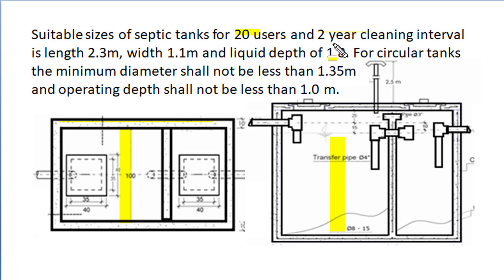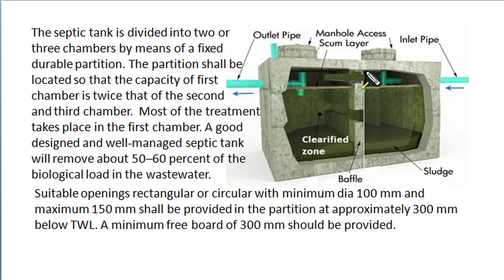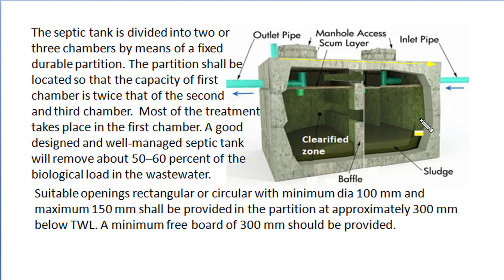For the same 20 users, if we need a circular tank, the minimum diameter of that tank shall not be less than 1.35 metres and operating liquid depth shall not be less than 1 metre. The construction of the septic tank can be illustrated by the diagram shown here with length, breadth and depth as indicated. The septic tank is divided into 2 or sometimes 3 chambers by means of a fixed durable partition.